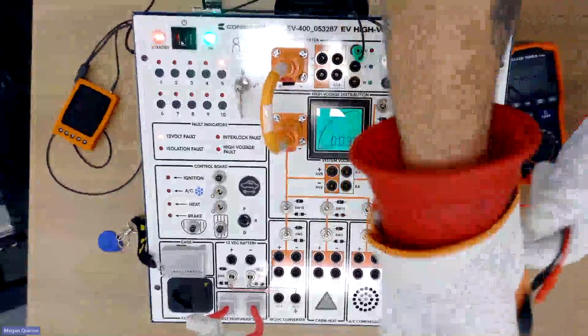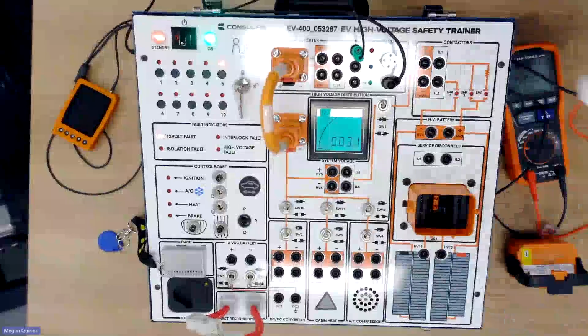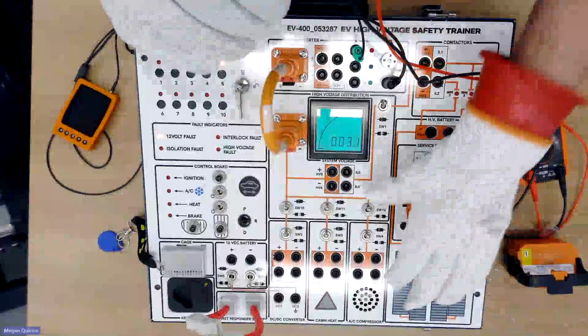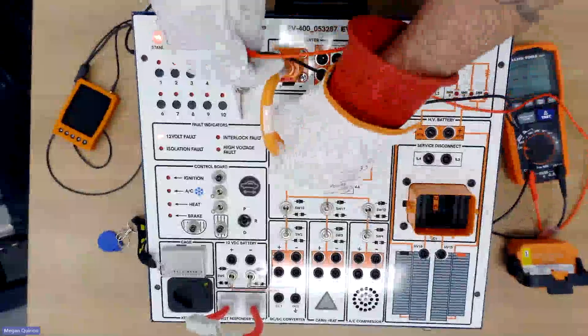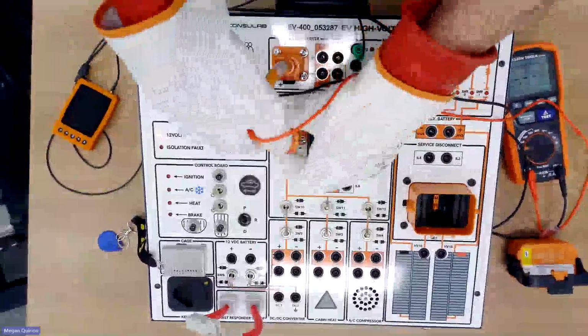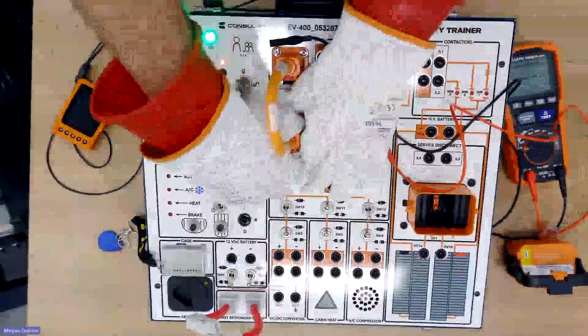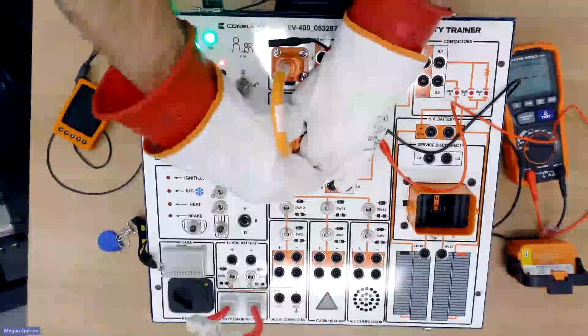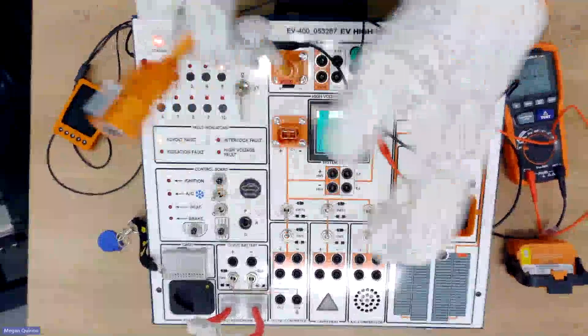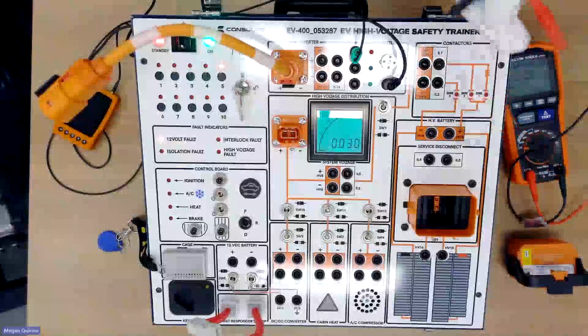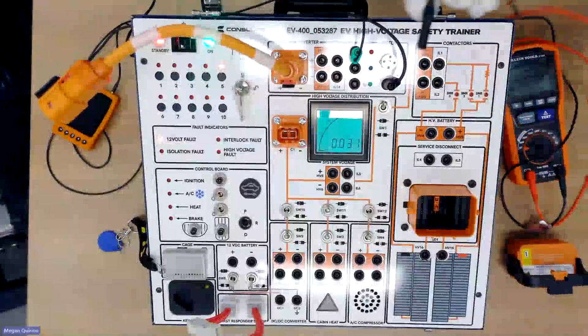Isolation testing requires that each individual component be tested independently. So with this tool, he's able to apply the 1,000 volts, as mentioned earlier, and look for an isolation fault. In this case, we're not going to go through the entire board. He's going to follow a procedure for isolating all the components, but we already know where the fault is, so he's going to go directly to it.